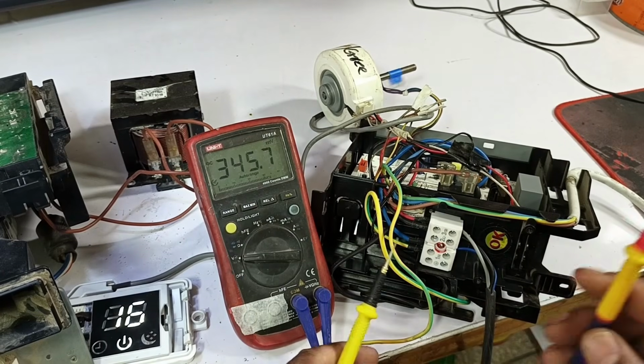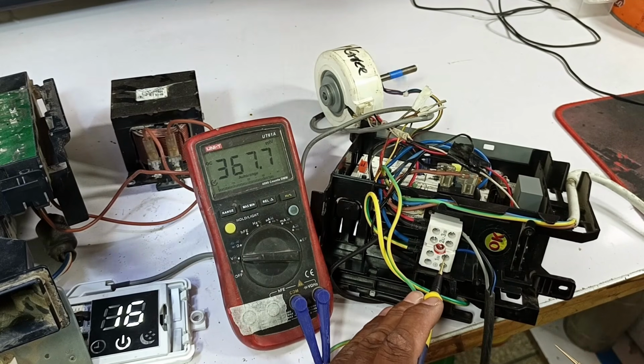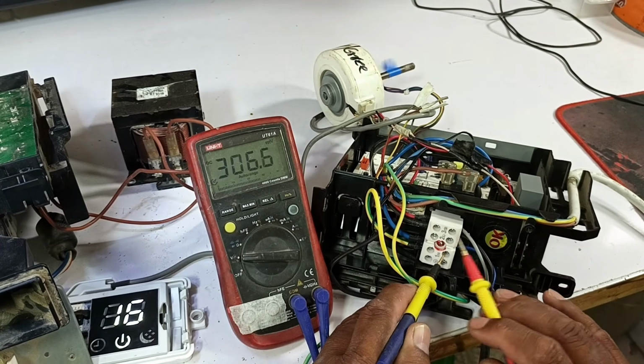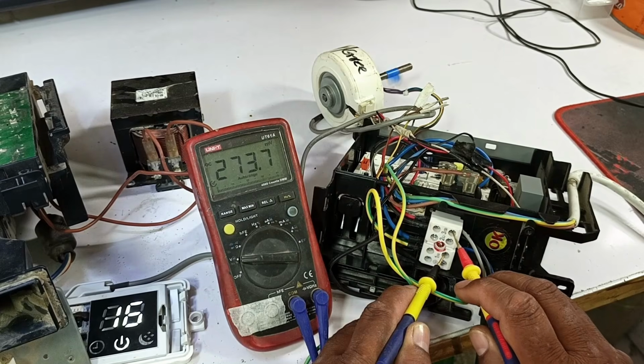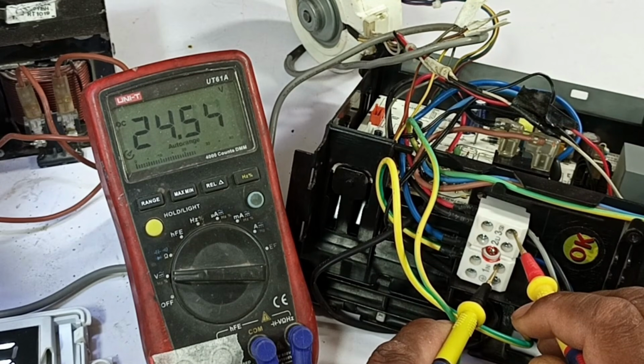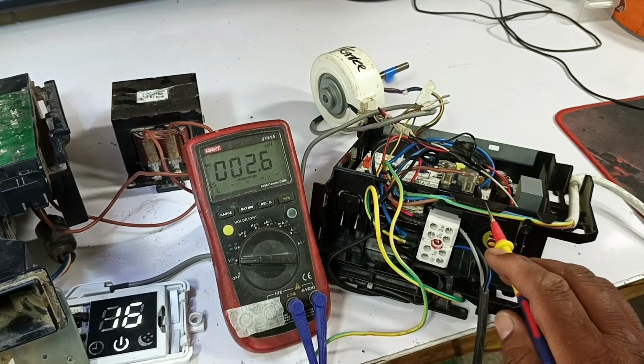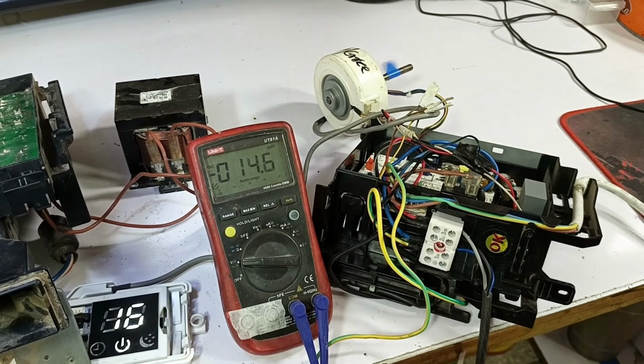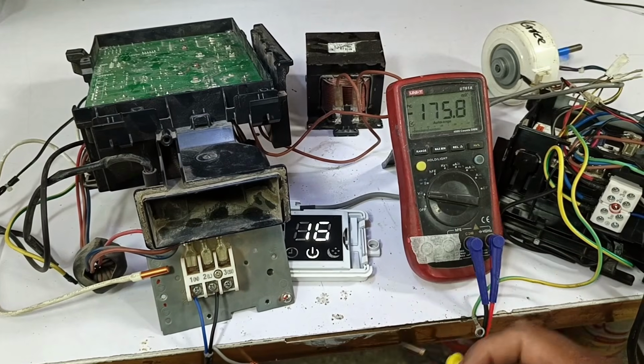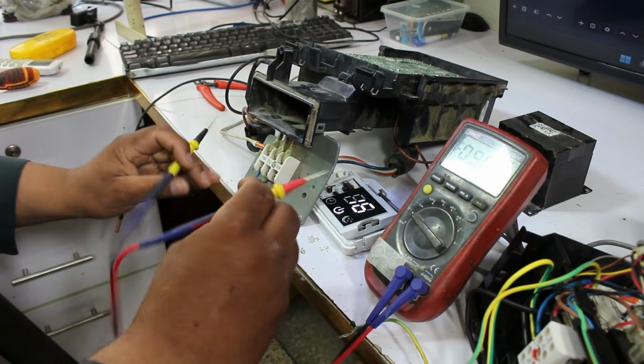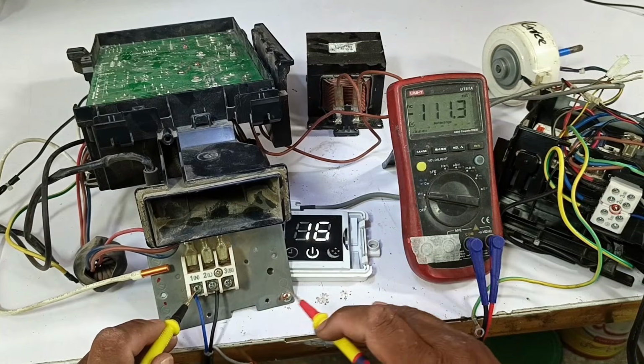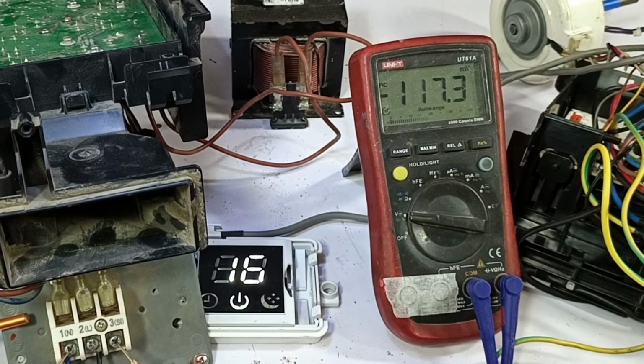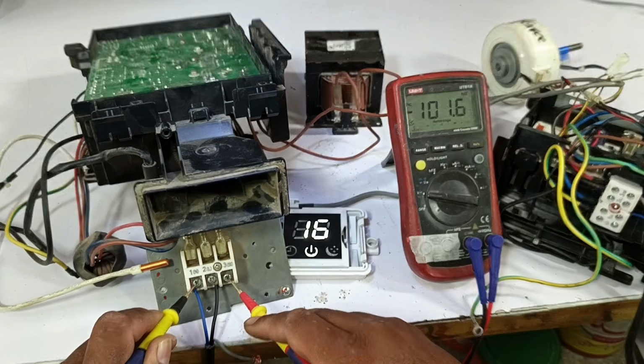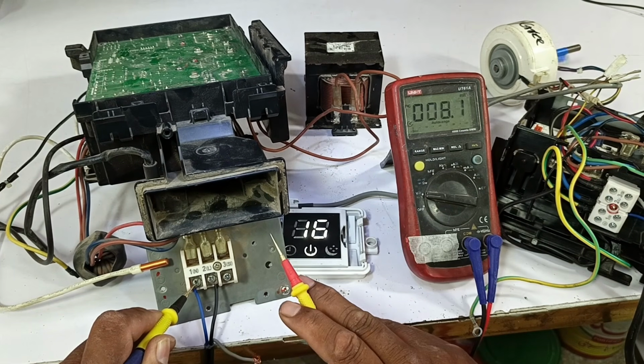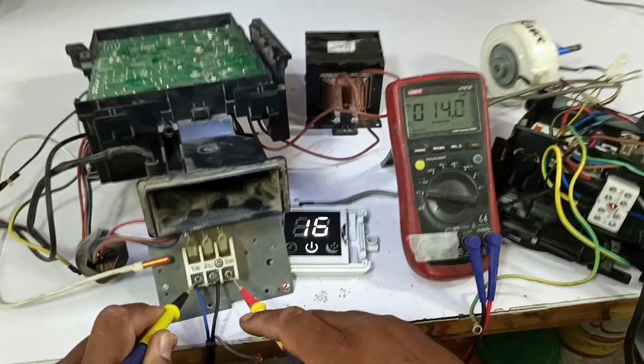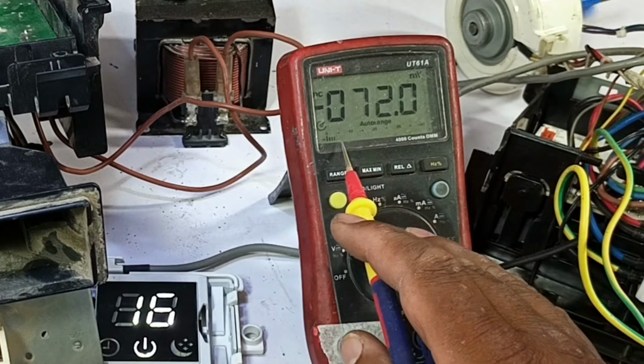Now I will first check on the indoor side. I will connect the neutral with the black probe, and the red probe I will place on the signal, which is number 3. So here you can see 24.94 volts are coming. This means that the voltage is being generated from here, which is important for communication. Now, in the same way, I will check the outdoor as well. So we will place the black probe on neutral at terminal number 1, and we will check on number 3. So here you can see that no voltages are being generated at all. Even if we lift the probe, nothing happens. Only a few millivolts are coming, and the bars below are fluctuating.